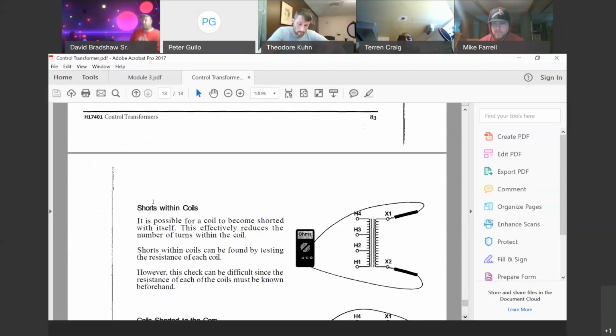Once again, they're looking for a short, testing across a short instead of an opening here. If I measure across the secondary side of the transformer and it zeroes out, showing maybe 0.1, 0.2, or 0.3, that's a short.